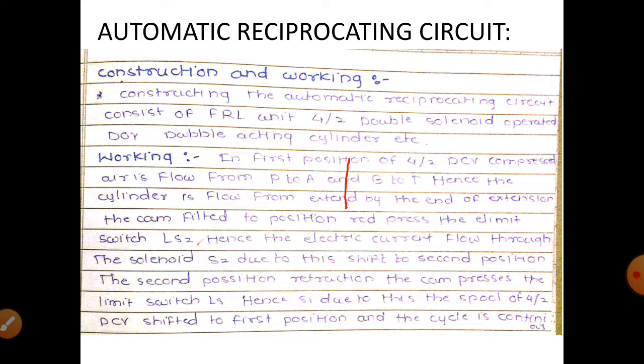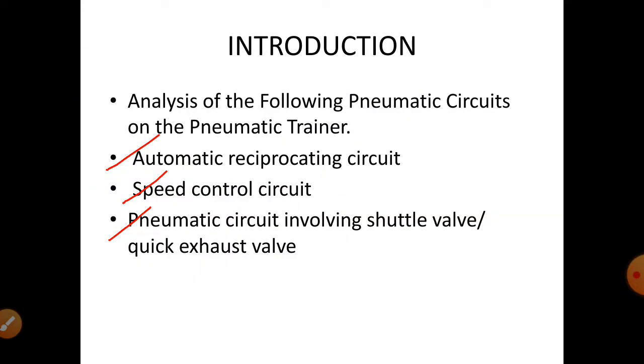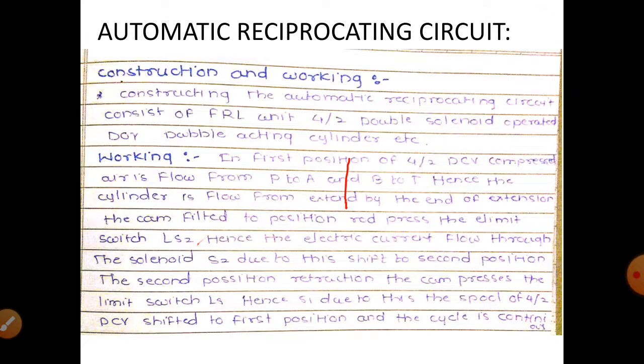The working of the automatic reciprocating circuit: in the first position of the 4x2 directional control valve, air flows from P to A and B to T. Hence the cylinder extends. The cam triggers limit switch LS2, causing electric current to flow through S2, which shifts the valve to the second position. In retraction, the cam presses limit switch LS1, causing S1 to shift the 4x2 directional control valve back to the first position, and the cycle continues.